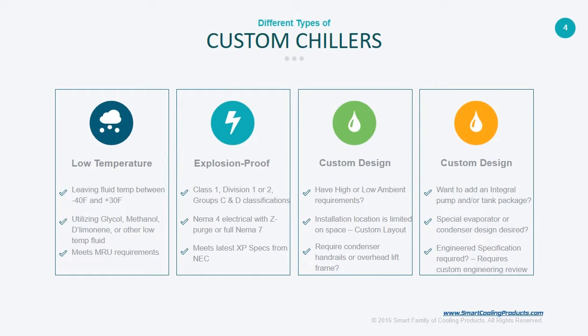The different kinds of applications we've got are basically low temp chillers, explosion proof chillers, and then, as we mentioned, the catch-all is just custom design chillers. Low temperature units, basically anything running from plus 30 degrees leaving fluid down to minus 40 F. Typical fluids used with these units are propylene or ethylene glycol, methanol, so it's usually a methanol water mix, D-limonene, which is a citrus-based fluid, Dynalene, which is another type of heat transfer fluid, and propylene oxide as well. We've been doing several units of those lately.